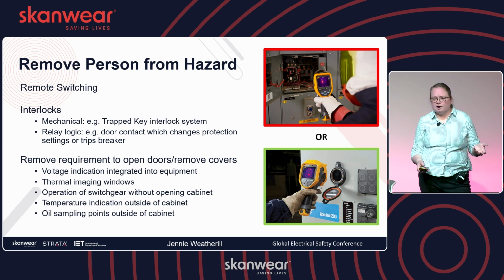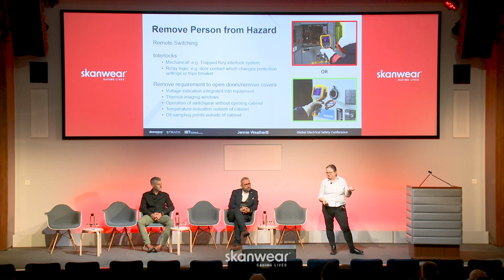Or remove the requirement to open doors or remove covers. The first one here can be controversial: voltage indication to show if the equipment's energized. People say, I'm not going to rely on that to prove dead. That's fair. But if I walk up to a piece of kit and the voltage indicator says it's live, I'm going to do some extra checking. I'm going to make sure I'm on the right piece of kit. I'm going to make sure my isolation's good. It's just one more layer that we can use to reduce that likelihood and therefore reduce that risk.